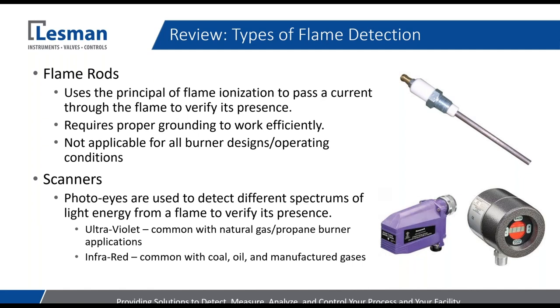A lot of flame rod issues just deal with the grounding. Not every application or every burner design is compatible with the flame rod. Customers like to use them because they are fail-safe and considerably less expensive than some UV scanners, but you'll have to talk to the burner manufacturer and look at their product availability to see if flame rods are suitable for that application.